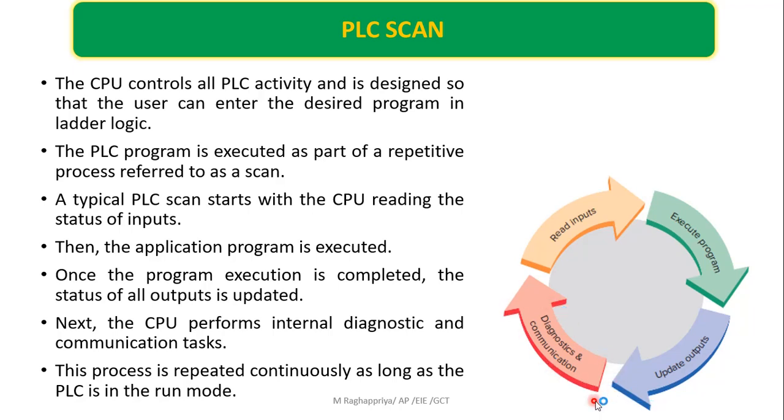And finally, diagnostics and communication. Diagnostics and communication is the internal task which the PLC performs. So this cycle repeats continuously. The moment it reads the input, it gives the data to the processor. The processor will execute the program and generate an output. That output will be given to the output devices. Again the diagnostic is performed. Then again the sensor input is read, the control signal is generated, the output is updated, and so on. So this follows a cyclic pattern, and this is what we call the PLC scan.